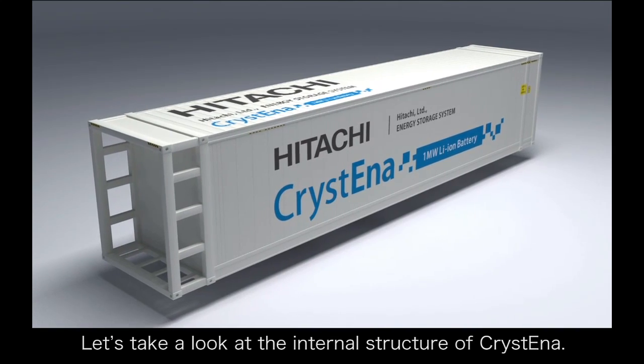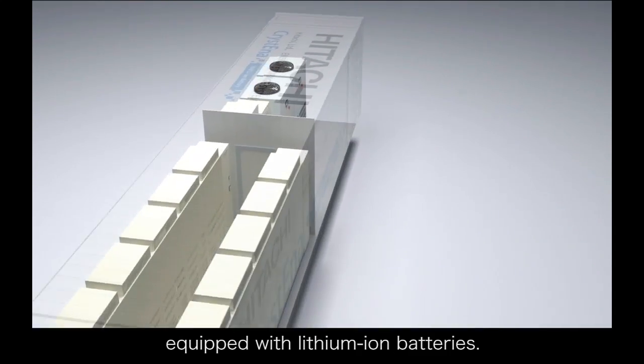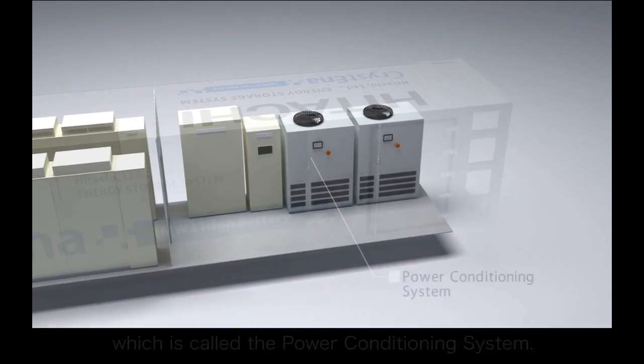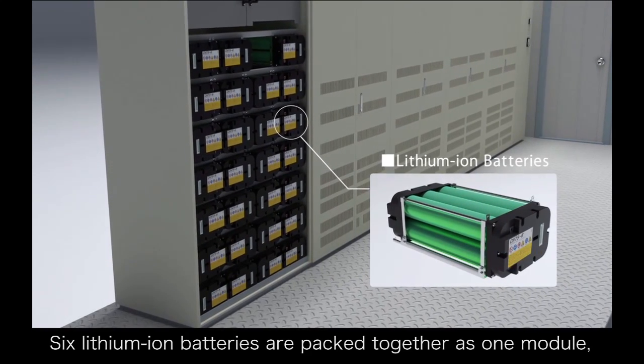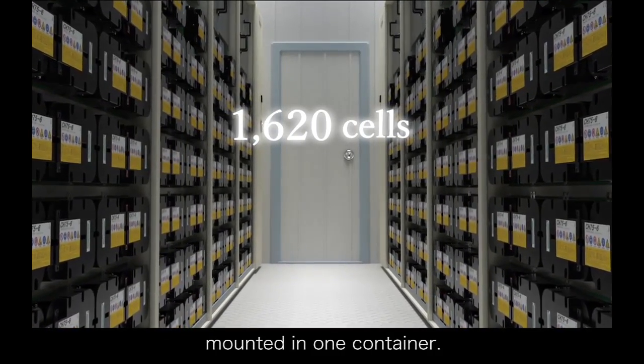Let's take a look at the internal structure of CrystEna. There are two rooms inside. The first room has battery panels equipped with lithium-ion batteries, and the second has a control unit and an inverter unit, which is called the power conditioning system. Six lithium-ion batteries are packed together as one module, and 27 modules are mounted in one battery panel. There are 10 panels lined up, so in total there are 1,620 lithium-ion batteries mounted in one container.